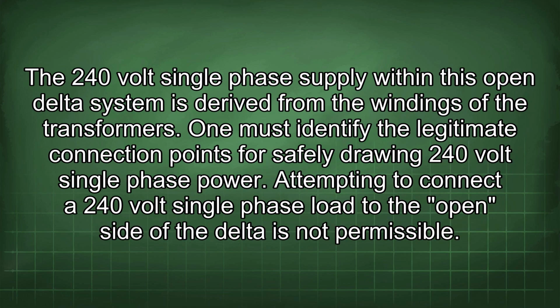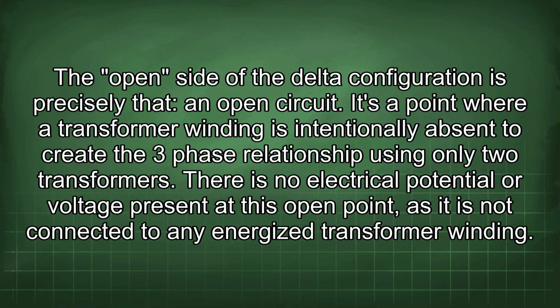The 240 volt single-phase supply within this open delta system is derived from the windings of the transformers. One must identify the legitimate connection points for safely drawing 240 volt single-phase power. Attempting to connect a 240 volt single-phase load to the open side of the delta is not permissible. The open side of the delta configuration is precisely that, an open circuit. It's a point where a transformer winding is intentionally absent to create the three-phase relationship using only two transformers.